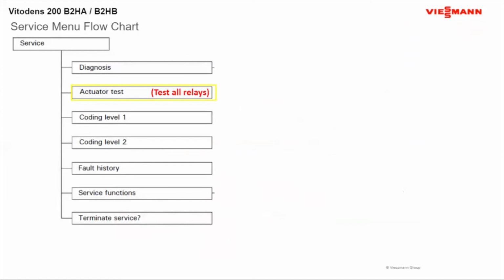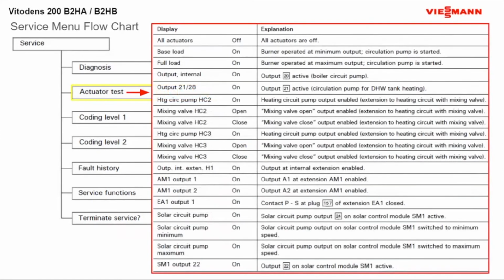Actuator test, this is what I find pretty neat for relay test as well as troubleshooting. When you click OK on the actuator test, it comes up with all actuators off. So none of these would be on when you first click on this. It will say off all the way down. As soon as you hit the down arrow and it highlights the base load, it automatically turns it into base load, puts it in low fire. So that's where you're going to go when you initially start this boiler, do service on this boiler.